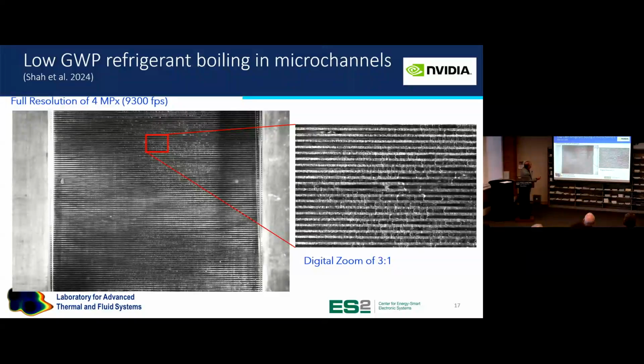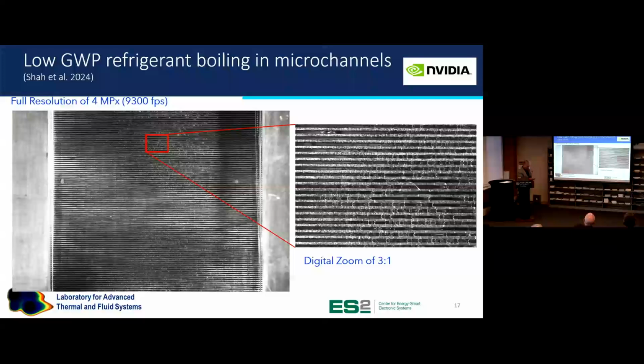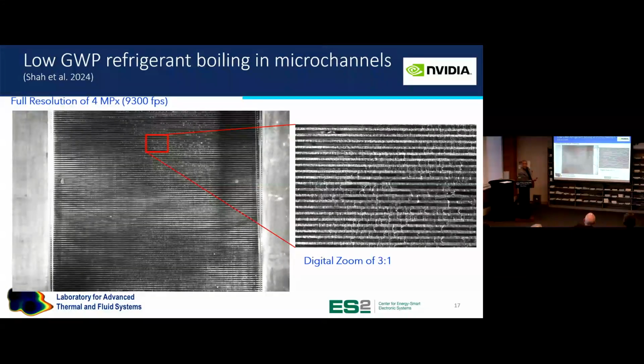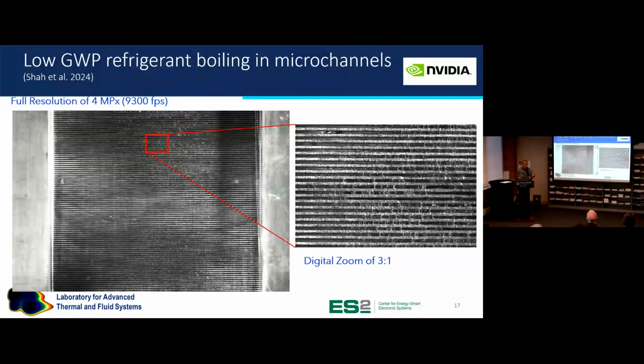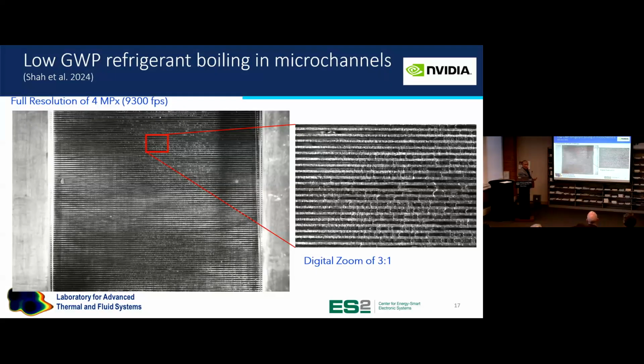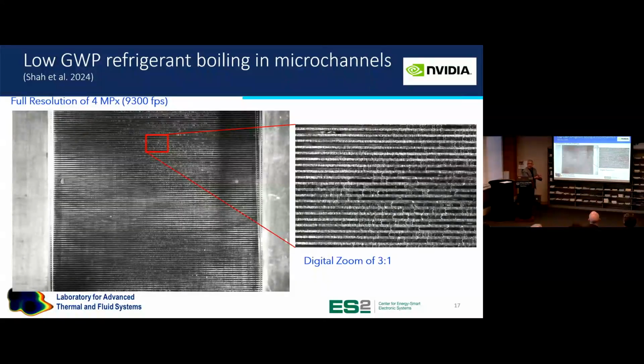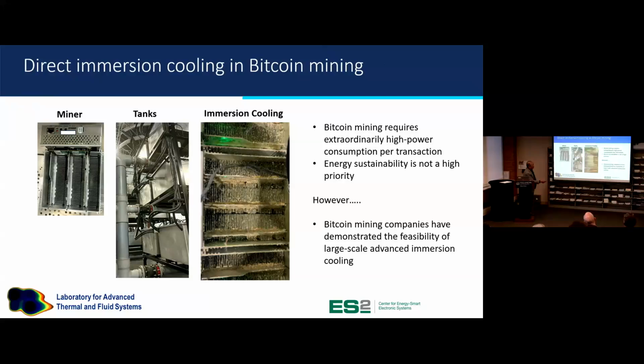So what you're looking at here is the flow through these small channels, called microchannels — very, very small. They're being heated from below, and as the flow comes through, it starts to change phase from liquid to vapor. Thanks to Shaw, my postdoc, for taking these beautiful images with a high-speed camera. If you zoom in, you can see the formation of individual vapor bubbles, which are absorbing the heat from this system and transporting it out of the cold plate.